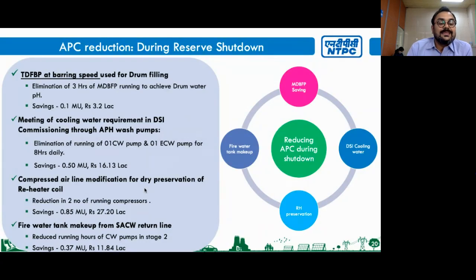So we have reduced the number of running compressors by 2, and that has saved us some power. Finally, the firewater tank makeup for stage 2. In our stage 2 units, we have the firewater tank makeup from the SACW return line. So generally, when the CW pumps are running, there is no problem of firewater tank makeup. But when the CW pumps are stopped in case of shutdown, we had to run CW pumps for our firewater tanks, and that was a costly thing.